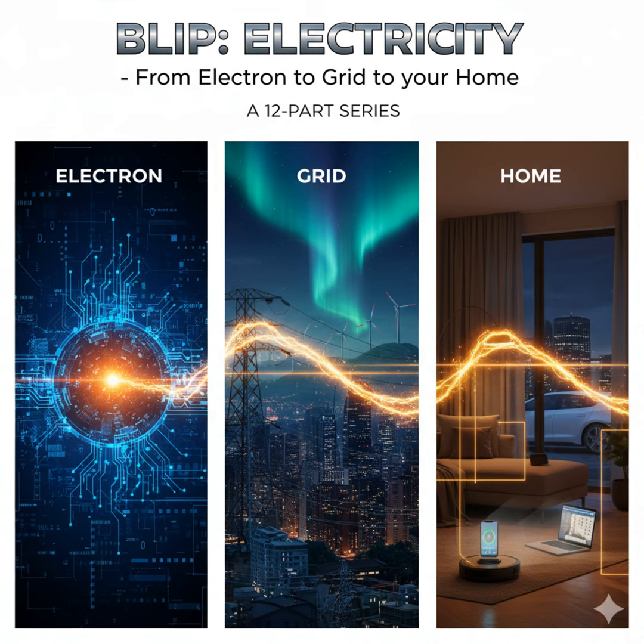Why is that speed and flexibility so critical for the modern grid? Give us an example. Think about a fault, like a short circuit on a major transmission line. When that line suddenly trips out, the power flow shifts dramatically onto parallel lines, and the voltage in that area tends to sag, sometimes severely. Okay, a sudden voltage drop. A static capacitor bank might switch on a step eventually, but it's slow. A StatCom, located nearby, sees that voltage drop instantly, and within milliseconds, injects a large amount of capacitive reactive power to prop the voltage back up. Like a shock absorber for voltage.